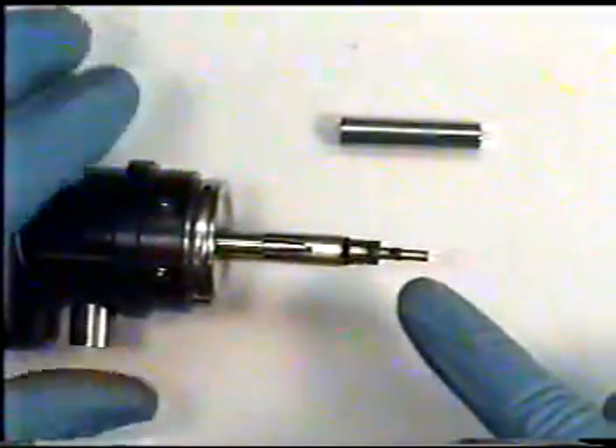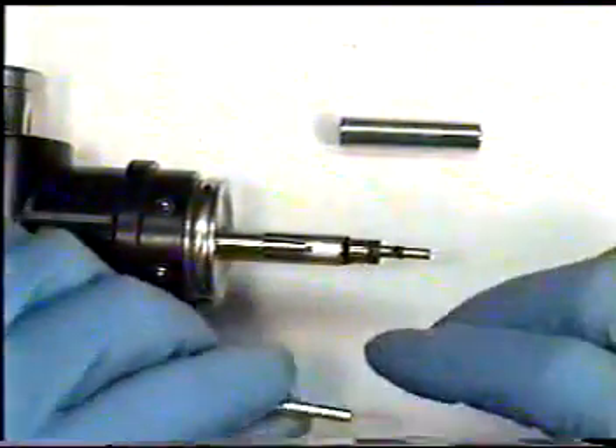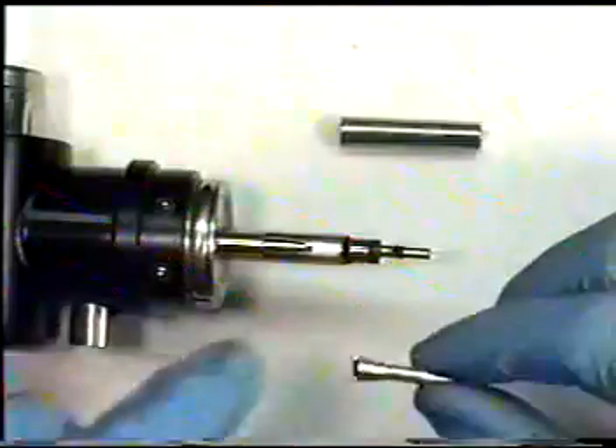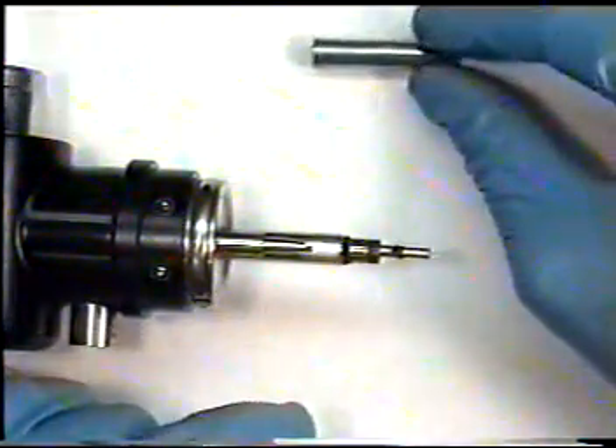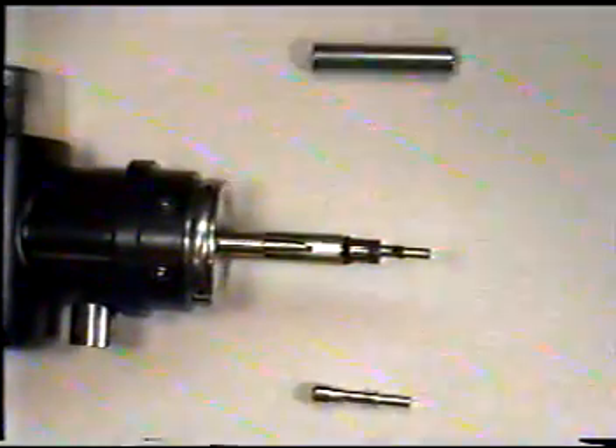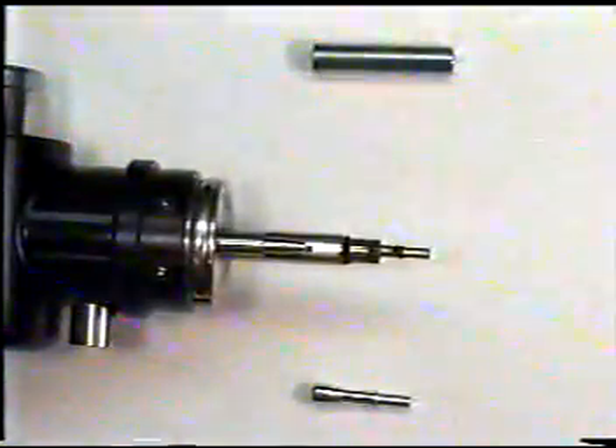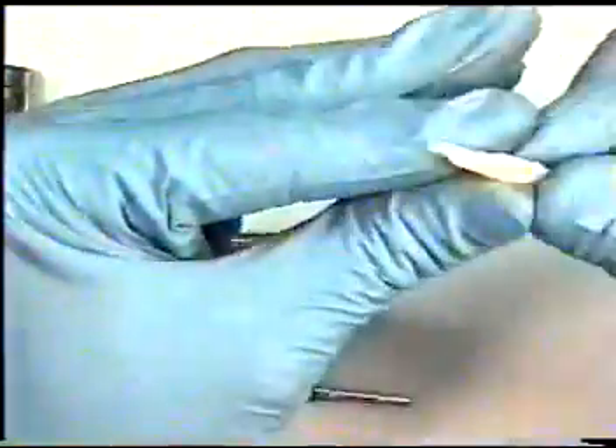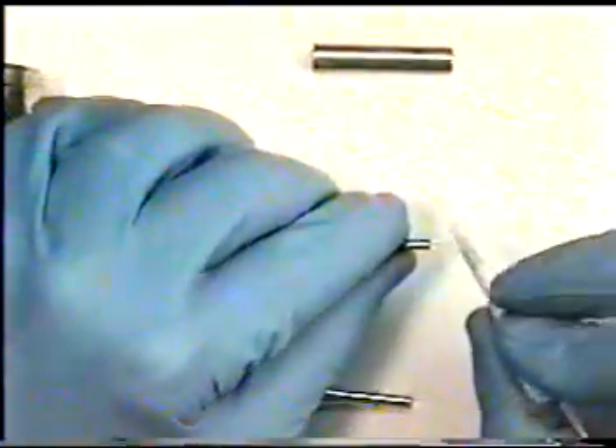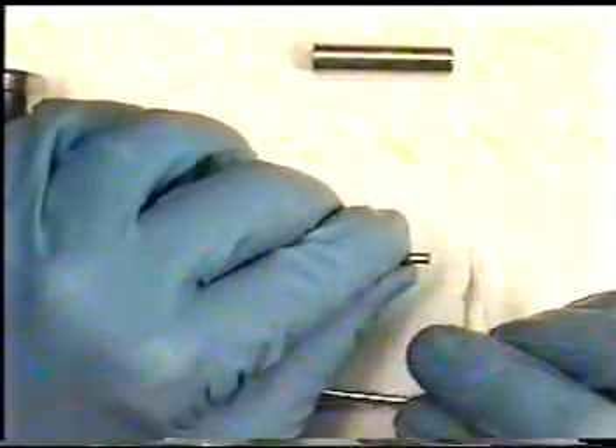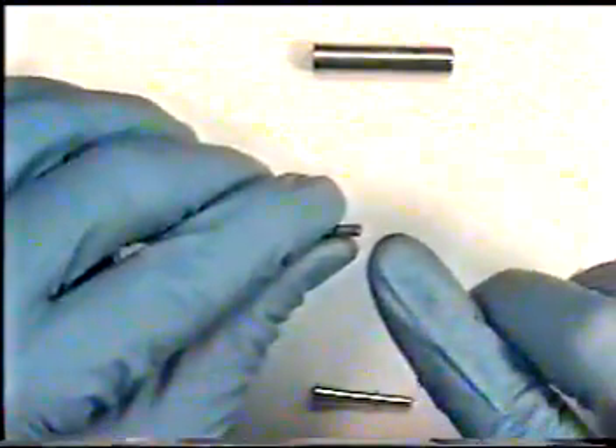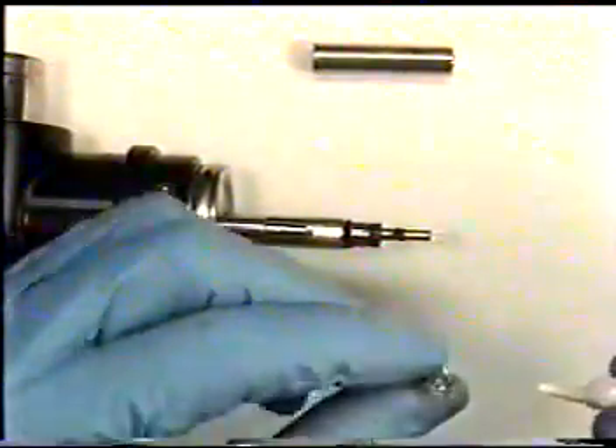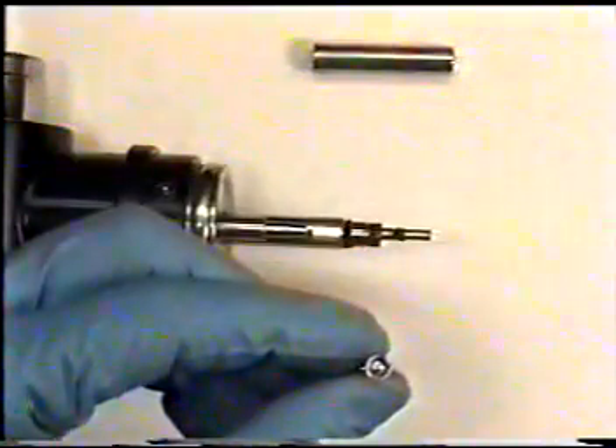Once the proximal fitting of your new light guide bundle has appeared from out of the light guide probe, you now need to retrieve your proximal end fitting and your proximal sleeve. We will need to clean both the sleeve and the proximal fitting to allow for proper light transmission. Using tissue paper, preferably lens paper, wrapped around a toothpick and some alcohol, clean first your brand new light guide probe proximal fitting to remove any debris from the tip. Second, clean out your proximal fitting. Any debris that has lodged inside the lens shaft must be removed. If necessary, use forced air, compressed air.